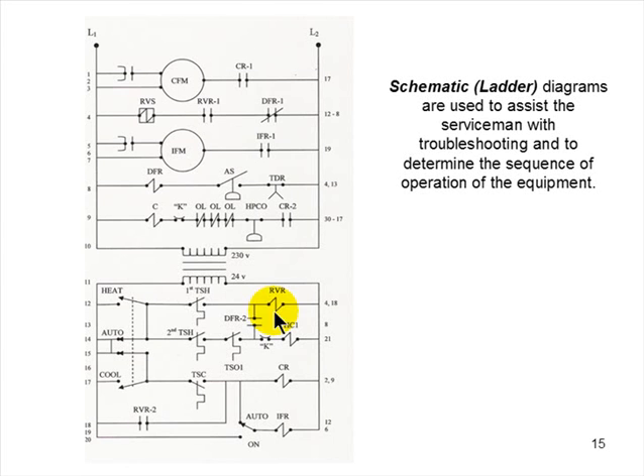If I look at this device, first thing I want to do is find the transformer, because the transformer is the dividing line, and it wouldn't matter if this whole thing were turned flat and the transformer were in the center. I'd have low voltage on the right and line voltage on the left, or tilt it the other way. It doesn't matter. But this is the line of demarcation. Everything above this, in this particular case, is line voltage. All these devices and switches. Everything below this transformer, because it's a step-down transformer, is low voltage.